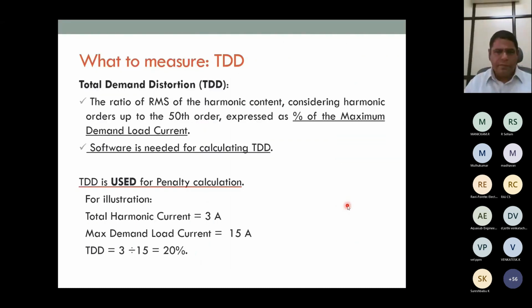So what to measure? The first thing we need to measure is TDD, which is called total demand distortion. This is the ratio of the harmonic content, summed up to the 50th order, expressed as a percentage of the maximum demand load current. Maximum demand load current will be detailed in the coming slides. For measuring TDD, we need software along with a meter. Without software, arriving at TDD will be difficult because there will be too many readings, and the software will help us find it within seconds.